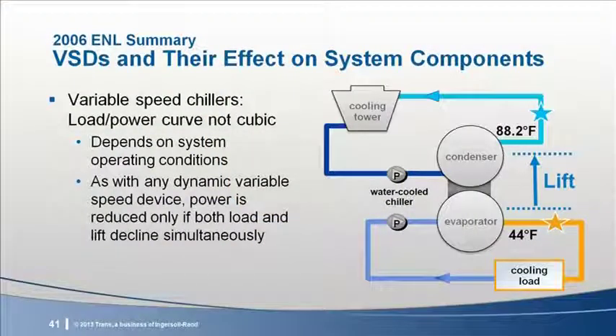Additionally, if the speed of the cooling tower fan and condenser water pump are reduced to save energy on those components, the chiller's leaving condenser water temperature is elevated, limiting the chiller's lift reduction. The bottom line is that the load and lift do not necessarily decrease in the correct proportion to allow a centrifugal compressor to approach the ideal speed and power reduction. Don't get me wrong, I believe adding a VFD to a centrifugal chiller's compressor almost always saves chiller operating energy on an annualized basis. But it is not always the most cost-effective place to spend our energy investment dollars.